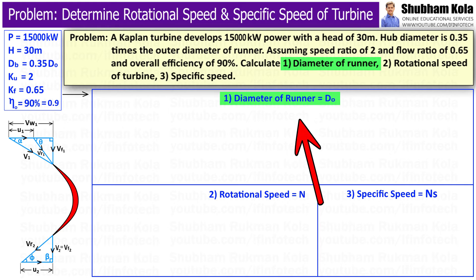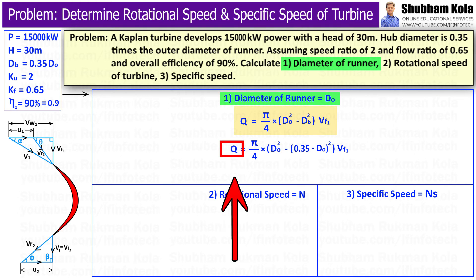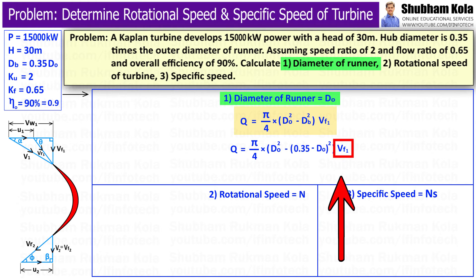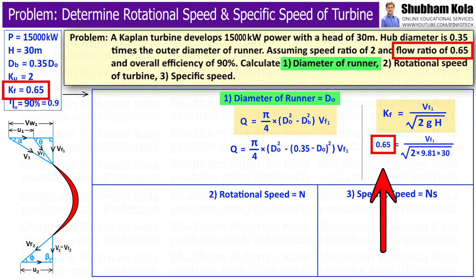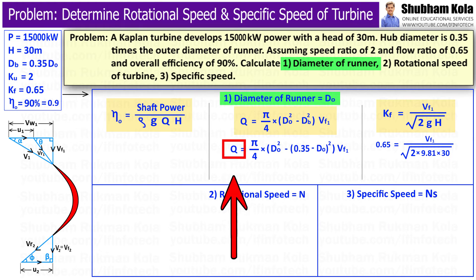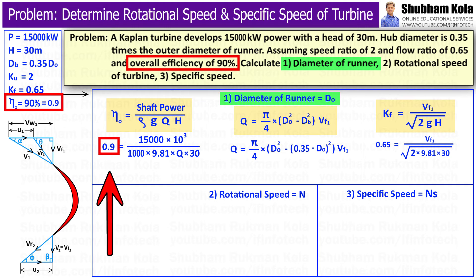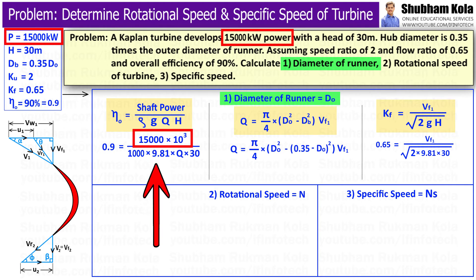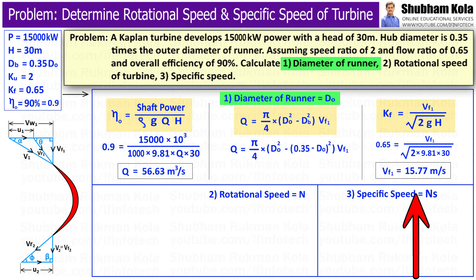First, we want to calculate the diameter of the runner using the discharge formula, writing db in terms of Do. We need to calculate discharge Q and velocity of flow at inlet Vf1. Vf1 can be calculated from the flow ratio, which is given as 0.65 with head 30 meters. Discharge Q is calculated from the overall efficiency formula — efficiency 0.9, shaft power 15,000 kW — giving Q equal to 56.63 m³/s and Vf1 equal to 15.77 m/s.